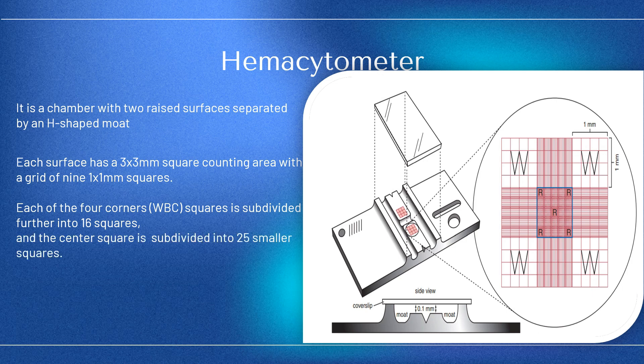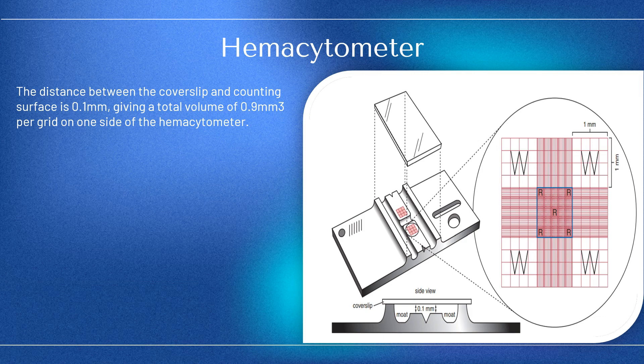A hemocytometer is a tool used in manual cell counting. It is a chamber with two raised surfaces separated by an H-shaped moat. Each surface has a 3x3 mm square counting area with a grid of 9 1x1 mm squares. Each of the four corner WBC squares is subdivided further into 16 squares, and the center square is subdivided into 25 smaller squares, each 0.2 by 0.2 mm. A coverslip sits on top, with a 0.1 mm distance to the counting surface, giving a total volume of 0.9 mm³ per grid on one side.